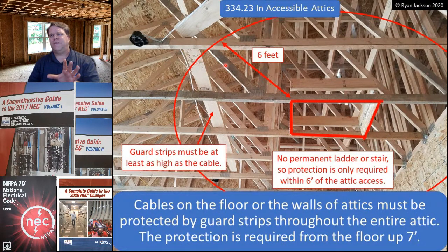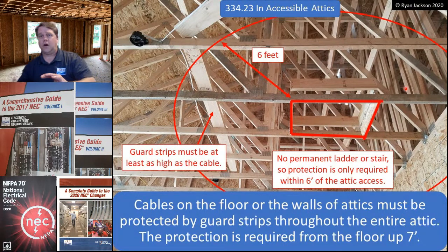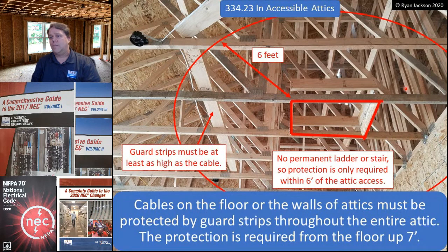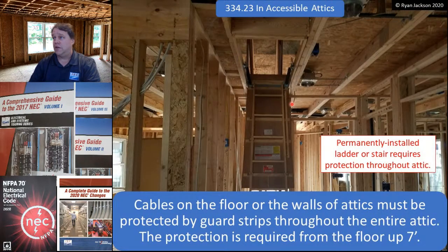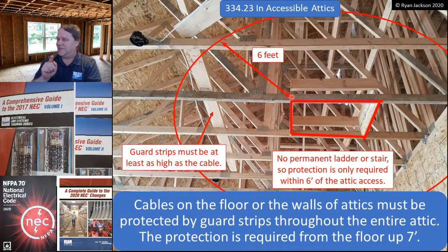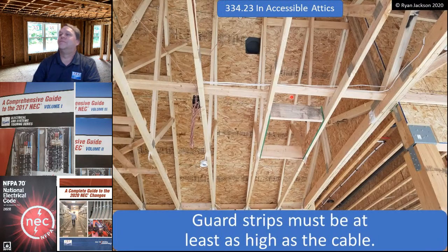And it's not something I would see very often in my area, but if I had the NM cable installed up higher, like 3 feet above the attic floor, then I would have to have running boards along it as well to protect it. But again, if there's no permanent stair, it's only within 6 feet. If there is a permanent stair, the whole attic from the floor, measured vertically, 7 feet. Let me know if you guys knew that or not, because I was wrong on that for 20 years.